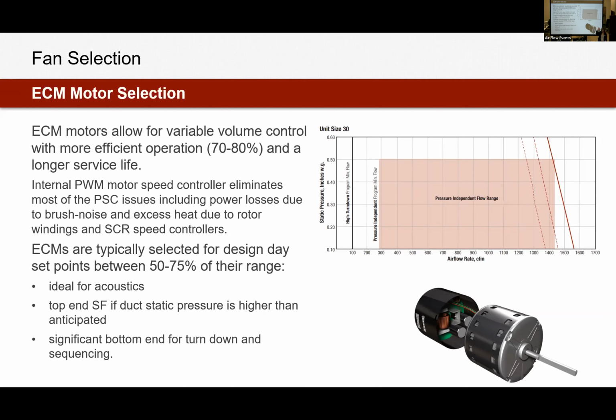Okay, back to fan curves and different motor programs. So Ryan pointed out that this ECM fan curve here has a ton of different lines and two different motor programs listed on it. Might be a little hard for you all to see, but inside of this red box here, we have one program called Pressure Independent Flow Program. Pressure Independent Flow Program actually allows an animation for this. Look at that. Pressure Independent Flow Program allows us to hold a consistent airflow regardless of changes in pressure. So this fan line right here, you can see how it's angled. Inside of that red box with that motor program, that line goes vertical. So our fan line will ultimately look like this.